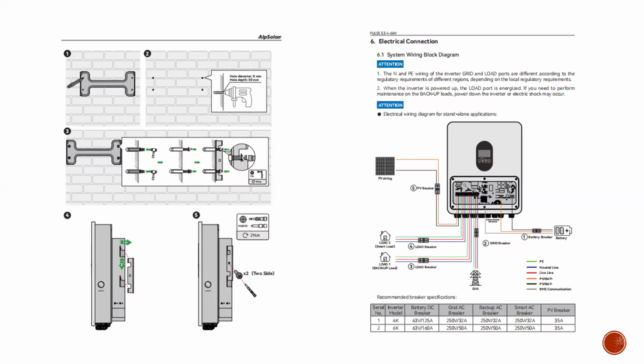And also, for your grid AC breaker, the recommended grid current for this unit is just 40 amps. So a 50 amps breaker is okay. Of course, many people use 63 amps, which is well popular in Nigeria, and it's still acceptable. The gap is not that much, right? 3 amps should work. And also for your AC, your load 1 breaker and your load 2 breaker, 50 amps is normal, it's okay for it.